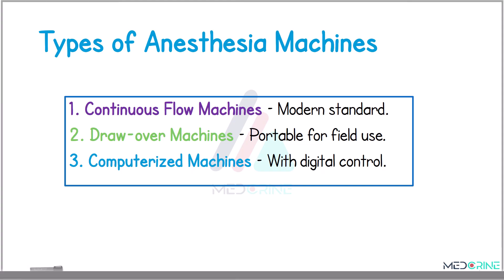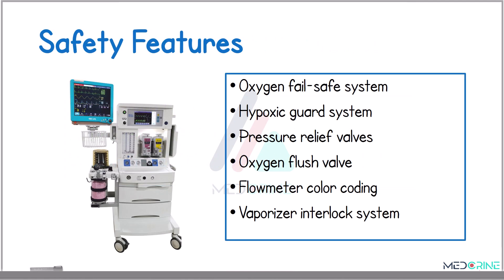There are several types of anesthesia machines. The three common types are the continuous flow machine, which is the standard anesthesia type in modern operating rooms; the draw-over machine, which is ideal for field use because of its portability; and a computerized machine that offers advanced digital control.